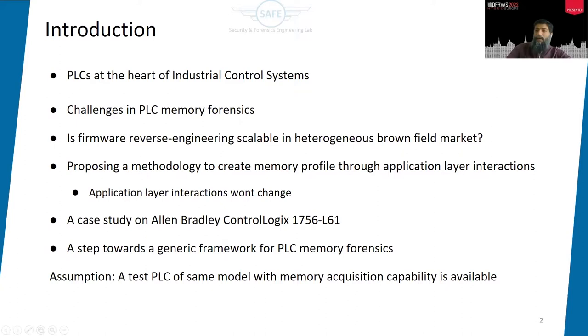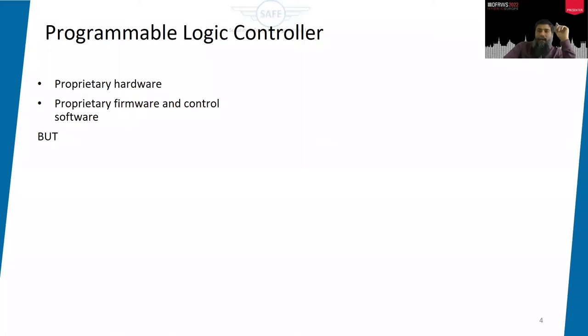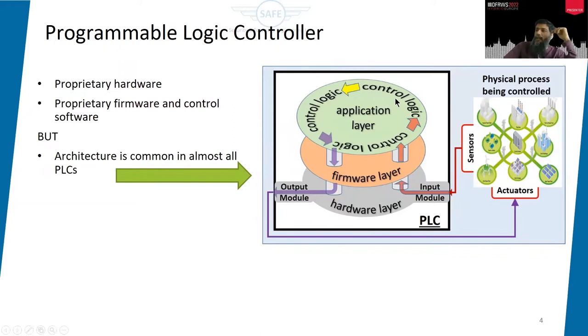Programmable logic controllers have a lot of proprietary hardware, firmware, and control software, but the architecture and function are usually similar. This is how a PLC functional diagram looks: we have a hardware layer controlled through firmware, and on top of that is an application, usually called control logic in ICS. The hardware has input modules connected to sensors from a physical process, and output modules connected to actuators.